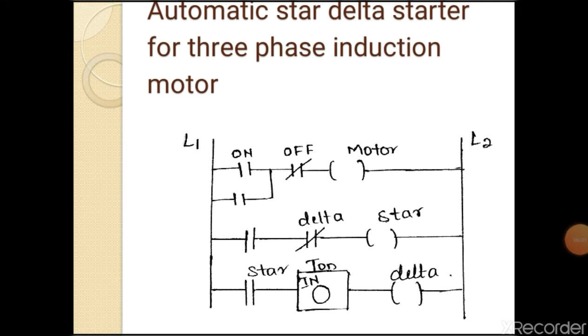Automatic star delta starter for three phase induction motor. In an automatic star delta starter delay is obtained by using a timer. The time delay can be adjusted by rotating the dial screw on the timer. The time setting is around 10 seconds for lightly loaded motors. For fully loaded motors the time setting is more than 10 seconds.